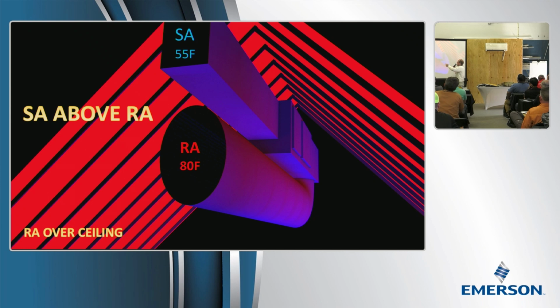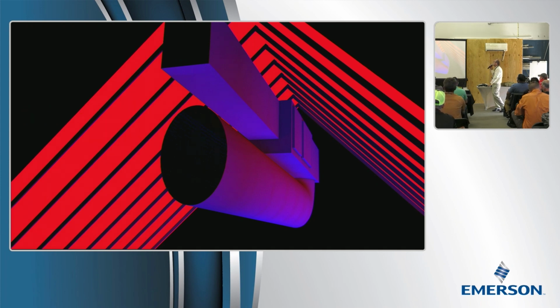Now, does a duct gain by heating up the supply air duct hurt the performance and comfort? No, that's reheat, baby. Duct gain on the supply side is great. What about return air duct gain? Now we have a penalty, because when you warm up the air going into an evaporator, things don't go the same way. So if we're going to get a duct hot, we always want it to be the supply, not the return. That's the one we can say, go ahead and bury in the insulation. We're not worried about it. Let's keep our coldest duct up on top and hung high for the best chance of success.